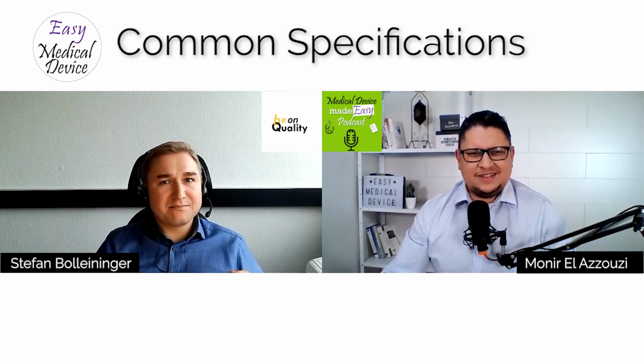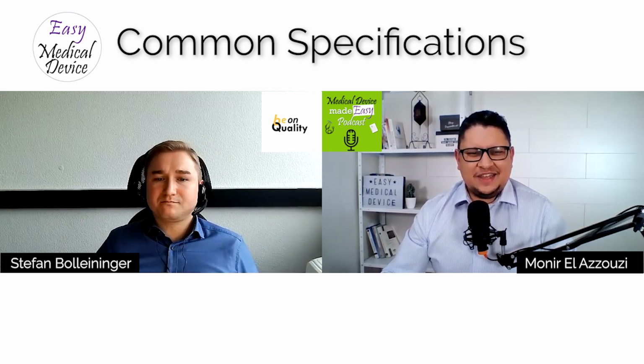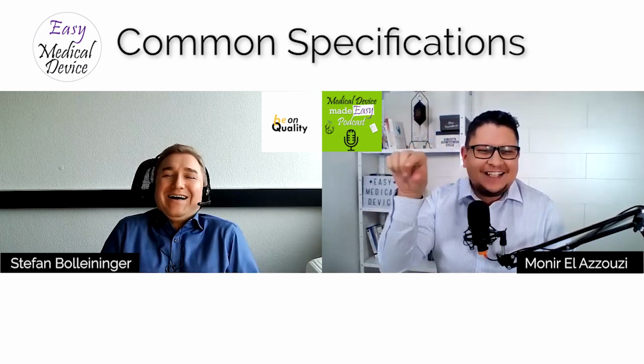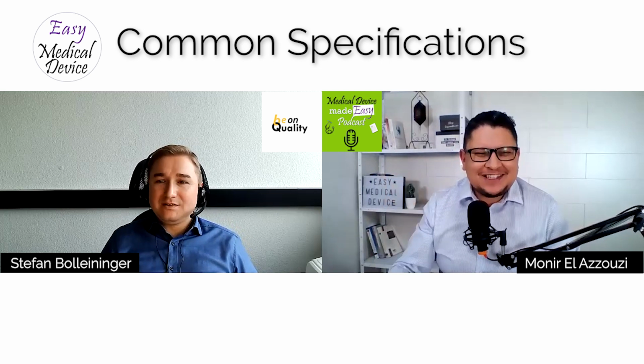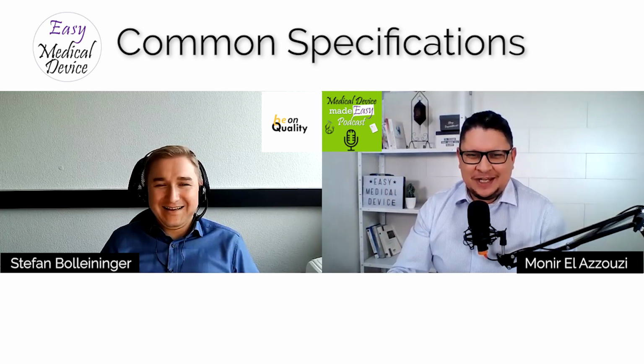Take that approach and always look at them carefully. Use those articles from it that you can really use and think are important for you. And always look at it with two words, shall and should. They always have a shall in it and some shoulds. The shoulds are, might be. The shalls are mandatory requirements. Use them carefully. I think we are used to that when we are reading ISO 13485. It's exactly the same principle. If you see a shall, you have to go through it. What I was doing was a search in the document on all the shalls, and each time I find a shall, I read it: what exactly is the requirement? It's the same methodology.